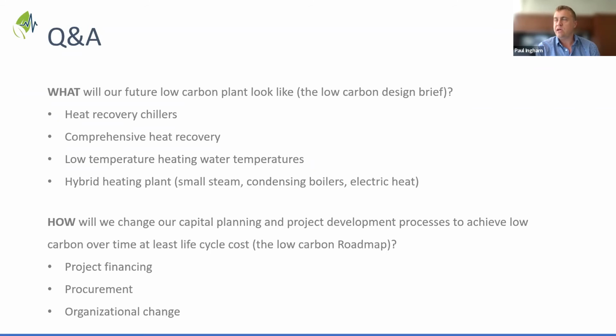On the second discussion, as we implement new technology, heat pumps, heat recovery chillers, we reduce the loads on the traditional boiler plants. Just use caution for unintended consequences. As we have a larger span between different seasonalities and the requirement for heat, make sure that the boiler plant can take the turn down, that reduction in load, and that you don't accidentally create a scenario where you have excessive cycling, excessive wear and tear, or you push the boilers out of a condensing mode. That would apply to condensing economizers as well, by recovering too much heat from something else, which negatively impacts the boiler system. So, a caution as you're going into good practice with good intention: understand it holistically from the heat load balance perspective. What is that going to do to your boilers, and how is that going to get you to the next stage gate?